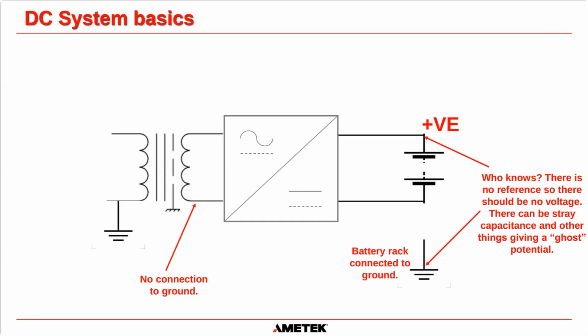There is no reference, so there should be no voltage. But once again, there can be stray capacitance and other things giving a ghost potential. But you will see that decay on your meter. And that's important, because when we get a few slides on, you will see that there can be circumstances, if it is a 135-volt system, that you could get 25 volts measured. But if it is a fixed 25 volts, then we have an issue. If it is a 25 volts that tends towards zero, then you know that your system is still completely floating free of the ground connection. Okay.